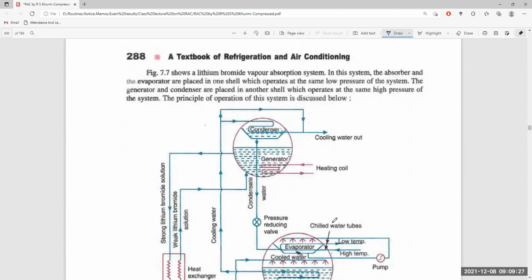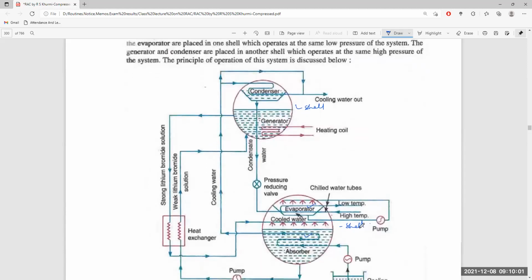Now, here we have a lithium bromide vapor absorption system. What we have? Two shells. One shell is here, another shell is here, and they operate at the low pressure and the high pressure of the system. Here absorber and evaporator are placed in one shell. This is evaporator and this is absorber. They are in the low pressure area, and generator and condenser are in the high pressure area, included in another shell.